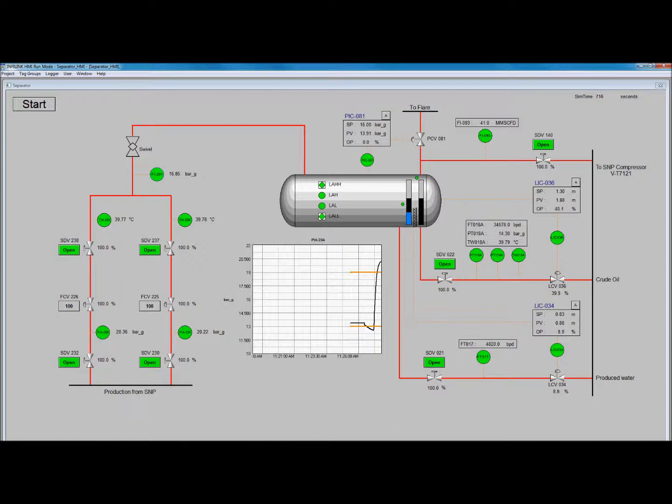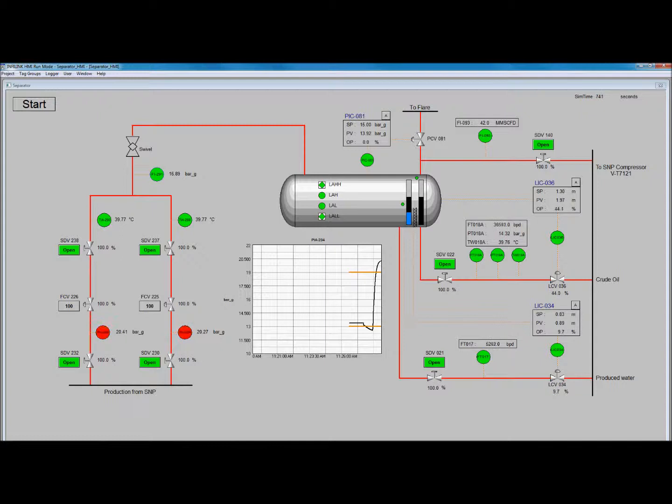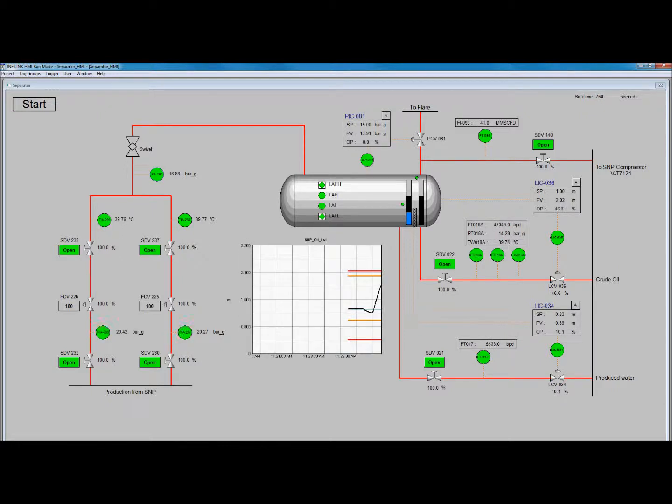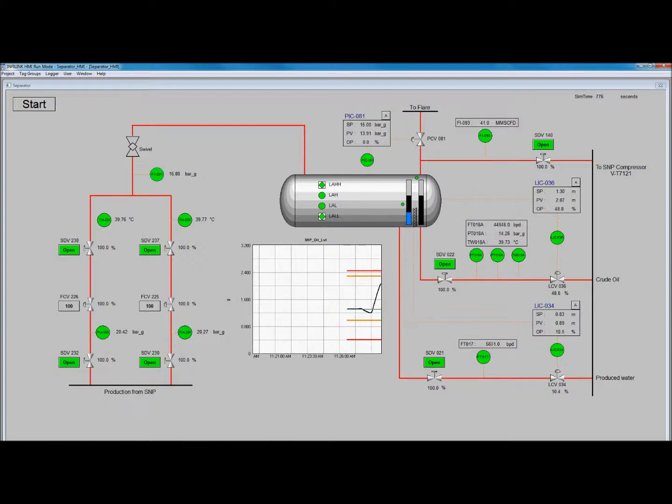However, because high pressure implies high flow rates, the separator may be in danger of overflowing. Let's check the strip chart. As you can see, the level also increased rapidly with the pressure and is approaching LAH.